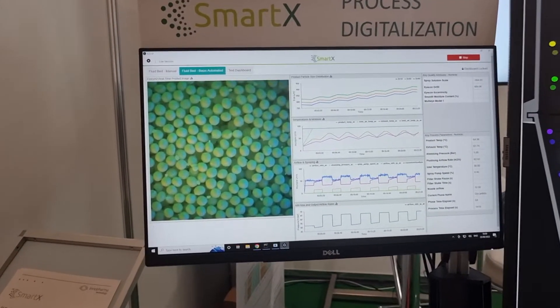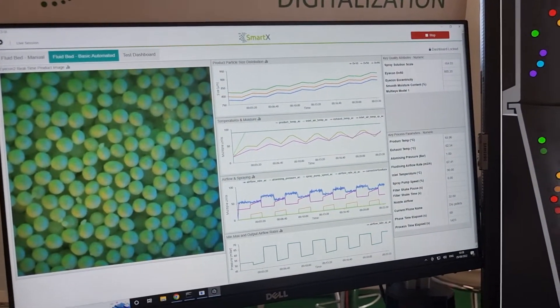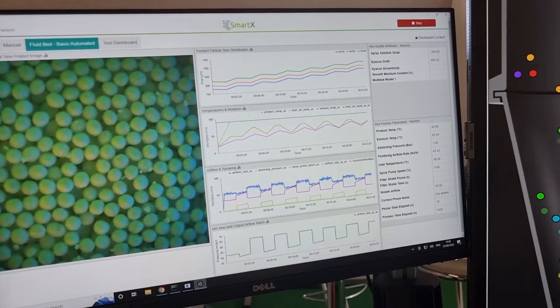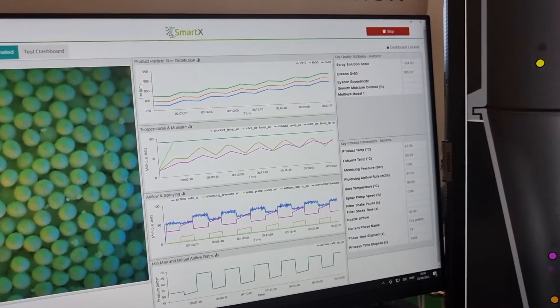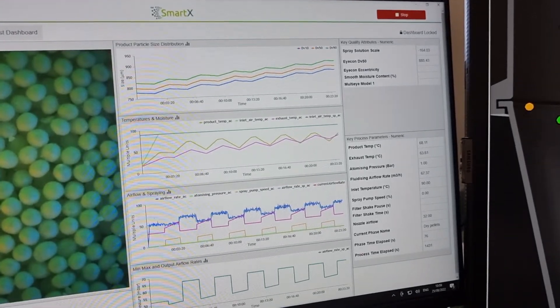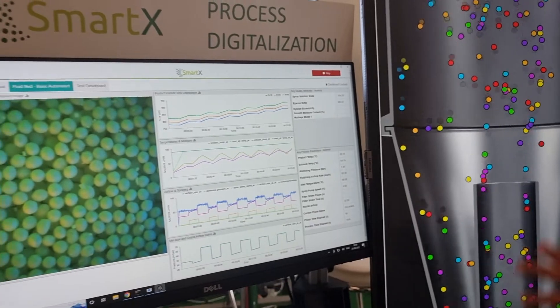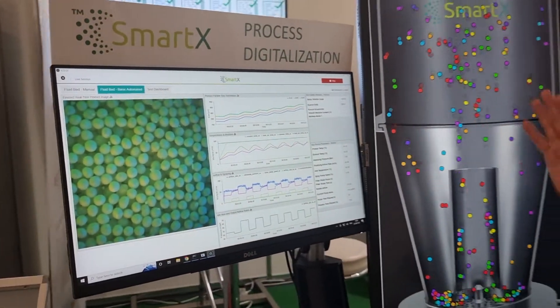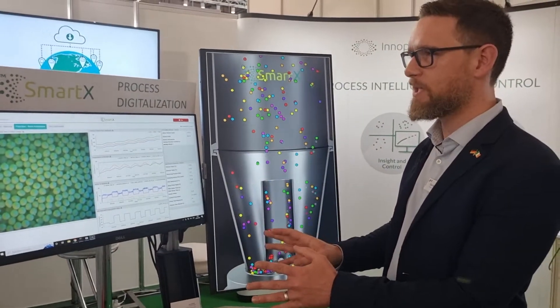We're reading the sensors from the Fluidbed, but we're also adding third-party sensors — our own and other sensors. The system is agnostic in that sense of what you can bring into it. We're controlling the particle size, or whatever end product quality you want — be it moisture content, et cetera — through this automated strategy. So it's completely hands-free. We've done this with feedback control built in here, and that is just one layer that we have with the SmartX system.